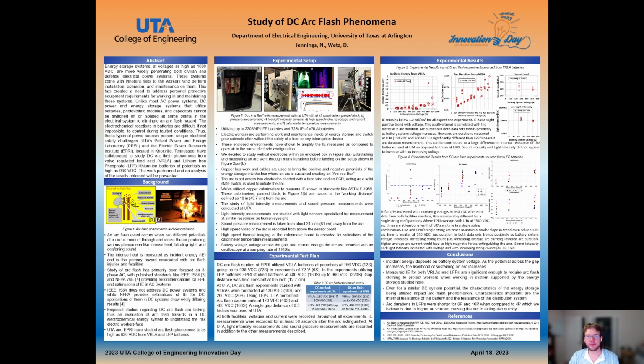The LFP data presented and studied by UTA and EPRI is shown here. UTA studied 3 different configurations of the batteries. We studied 4P, 8P, and 16 parallel cells, meaning that we would take a module with 4P20S cells and parallel it up to 2 or 4 times. In this data, we can see that the paralleling count for instant energy does not matter that much, as we have a very high 4P instant energy release and a very high 16P instant energy release as well.